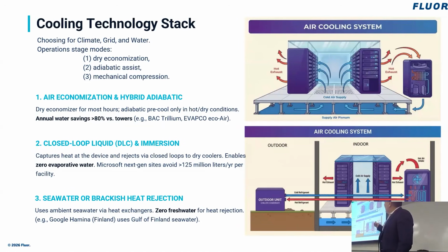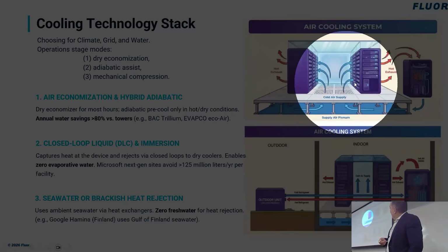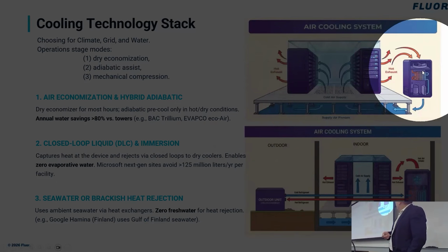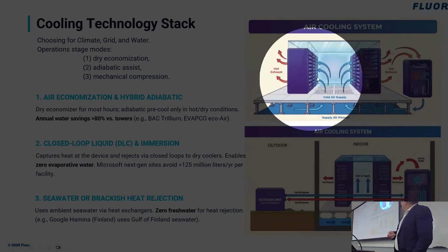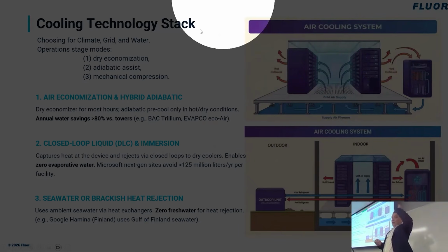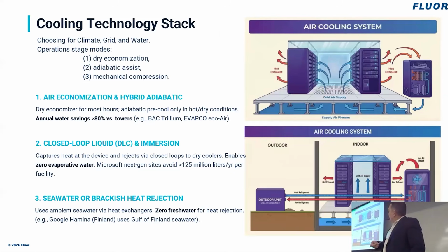So to have an idea, going back to the simple idea at the beginning, this used to be the traditional way of cooling the system, just using air. Normally we used to have a heat exchanger in the back, a plenum. The cold air comes in through the front of the rack, and the hot exhaust is taken, probably by a duct or some fan, to send it back to the cooling unit.